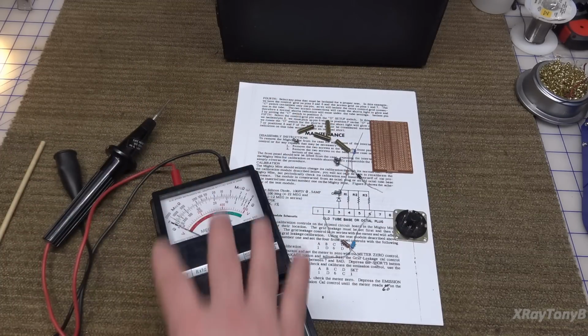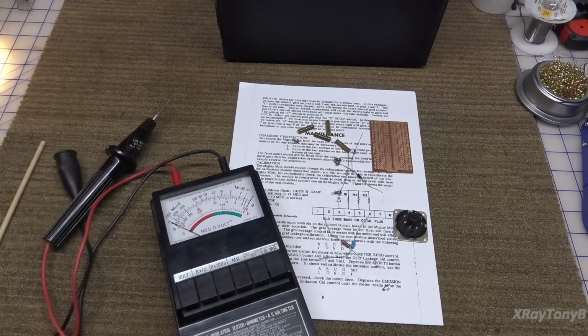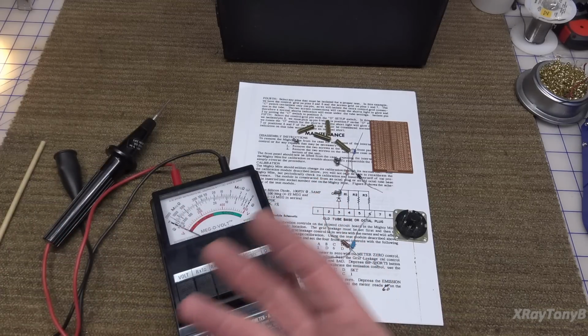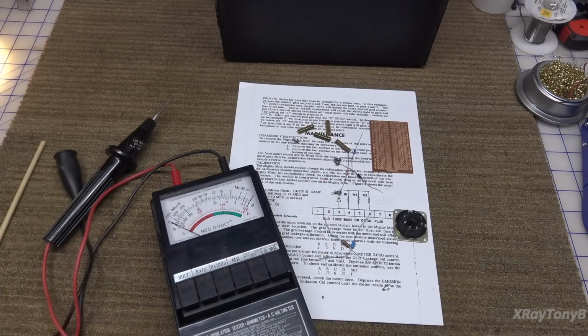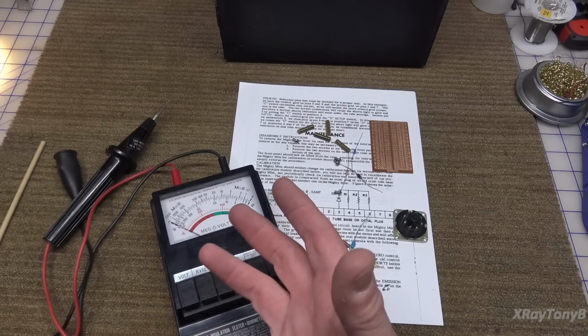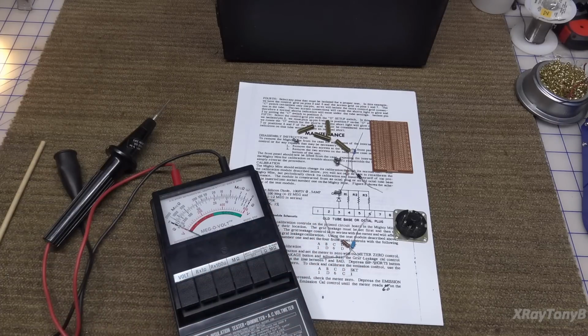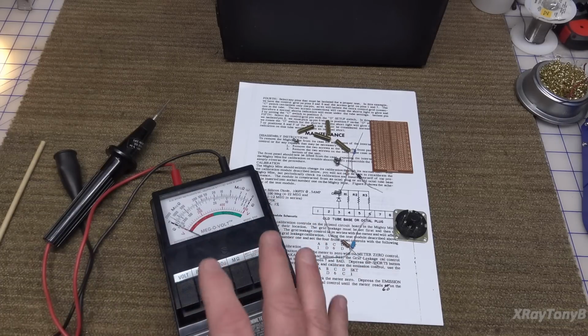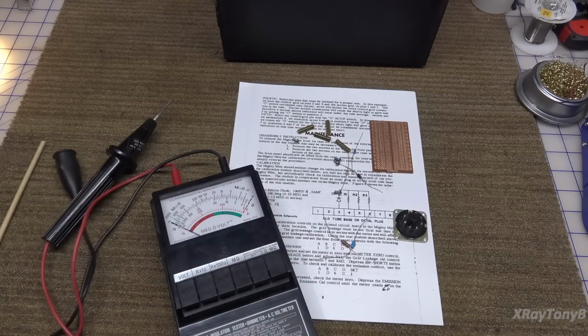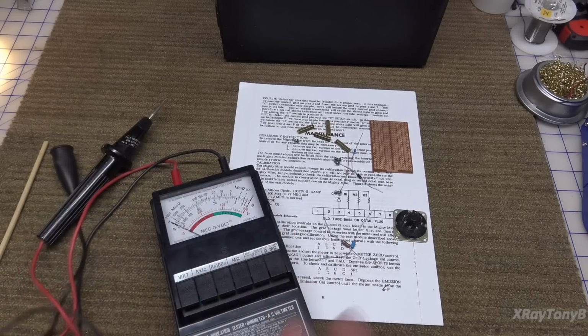And it'll cause it to kind of arc over, and you can actually see the resistance in there. You can see that there is a partial short. And that will eventually, when you get really high voltages on it, break down really hard and act almost like a dead short. It'll even burn the wire eventually, and that happens. But it sometimes can be difficult to troubleshoot that without something like this. So that's what they're used for, at least for us.